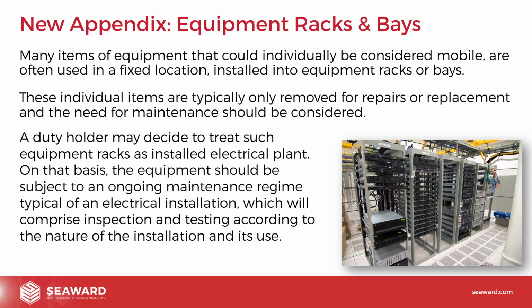Many items of equipment that could individually be considered mobile are often used in a fixed location, installed into equipment racks or bays. These individual items are typically only removed for repair or replacement, and the need for maintenance should be considered. A duty holder may decide to treat such equipment racks as installed plant, and on that basis the equipment should be subjected to an ongoing maintenance regime, typical of an electrical installation, which will comprise inspection and testing according to the nature of the installation and its use.